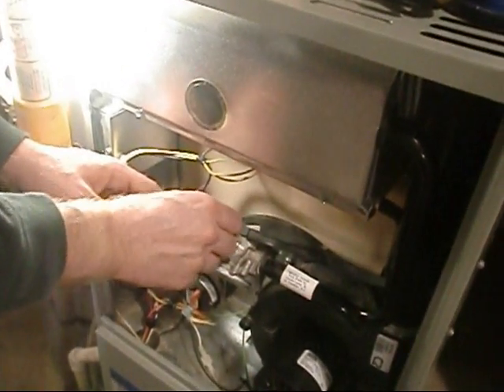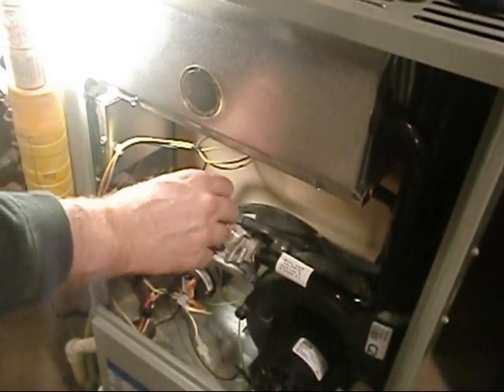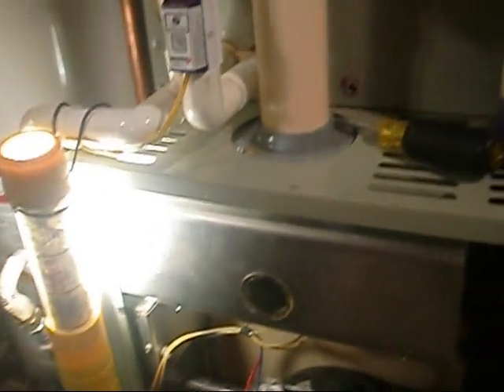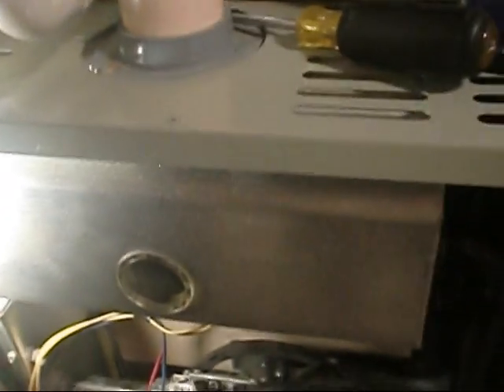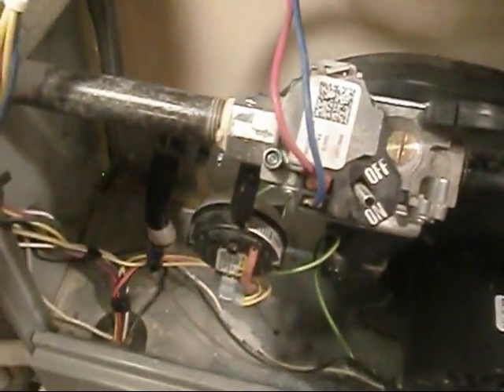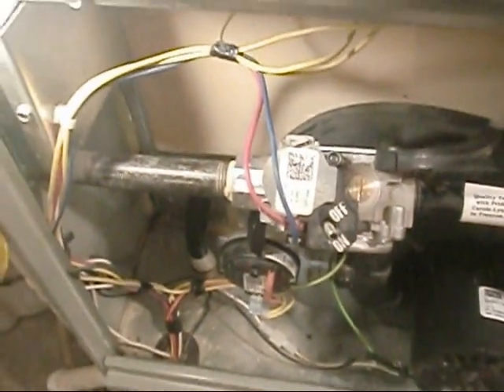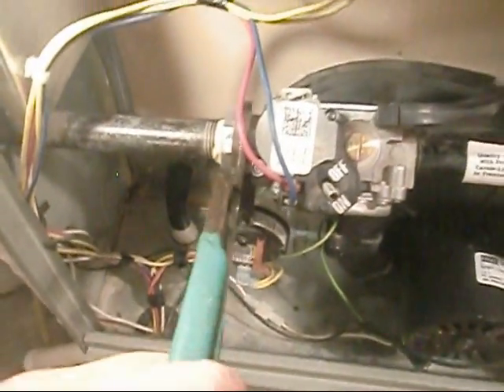Absolutely, absolutely. So you turn it. Alright, it's back in there, brother. Let's, and we got a pair of channel locks right there, we'll put that back where it was. Get a good grip on it, that's where you need to grip on anything on a gas valve right here. And you usually use a standoff too, another set of channel locks to do it. Alright, here we go. Okay, we're good to go.